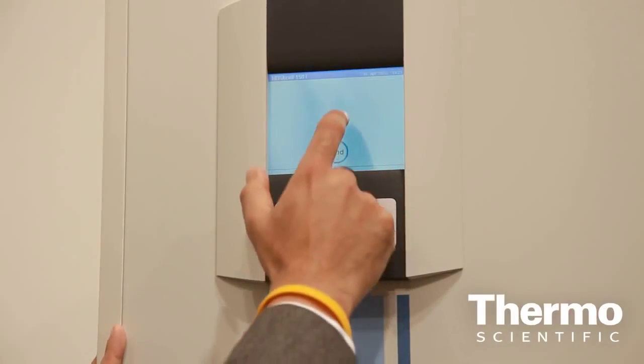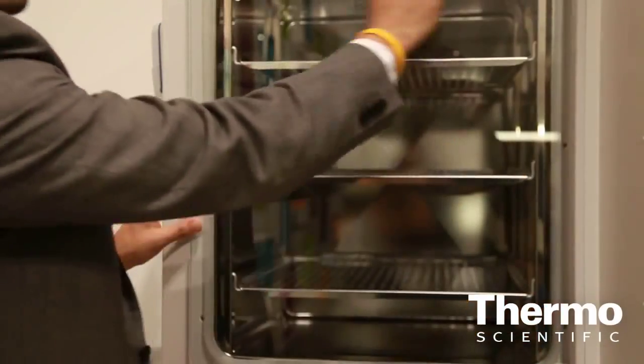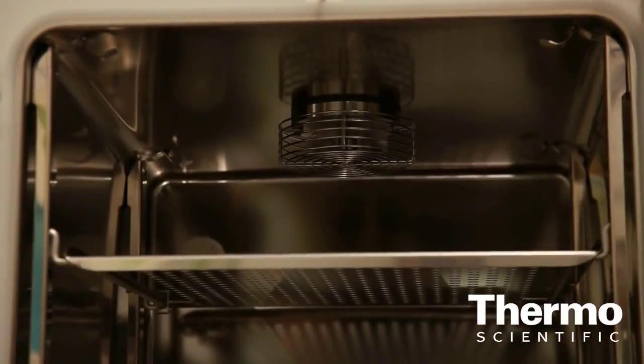And how exactly are we doing with this innovation? With IonGuard being just the next in a series of innovations that we've introduced, it's a silver antimicrobial matrix which covers all the internal surfaces. What that means is you eliminate 99.9% of the most common microorganisms within 24 hours. The benefit to the user is that they have peace of mind where they can prevent the contamination occurring in the first place, rather than having to think about cleaning the incubator after decontamination has occurred.